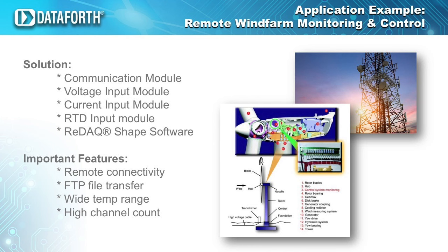In sum, the challenging environments in which wind turbines operate demand reliable and broad-ranging monitoring, control, and protection. Sensors are used to measure as many as 500 parameters in a modern wind turbine. Conditions that can be monitored include, but are not limited to, generator voltage, current, and frequency, shaft rotation speed, vibration in nacelle, rotor blade, and bearings, and hydraulic pressure. Possible temperature measurements include outside air temperature, drive shaft and gearbox bearing temperatures, and generator temperature.